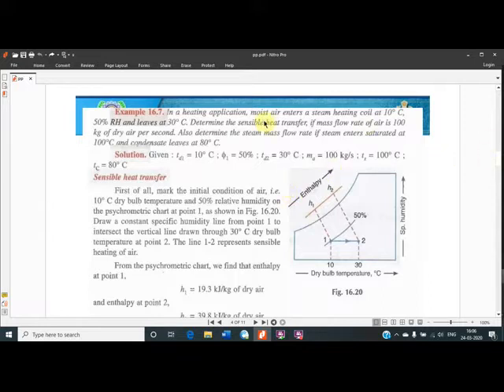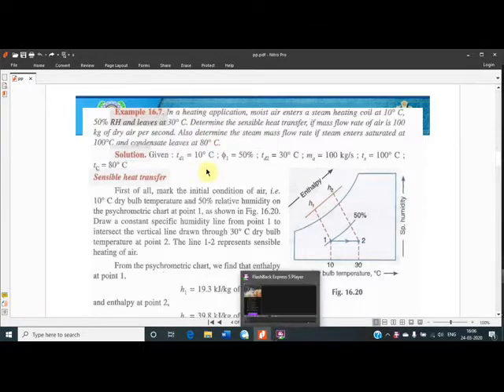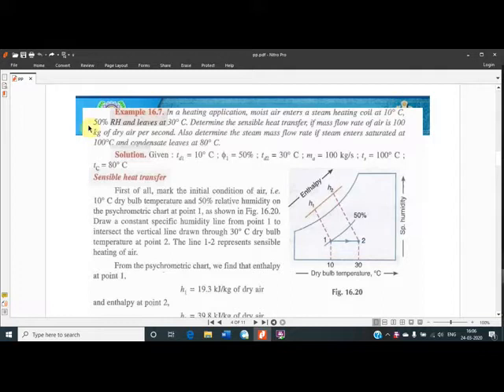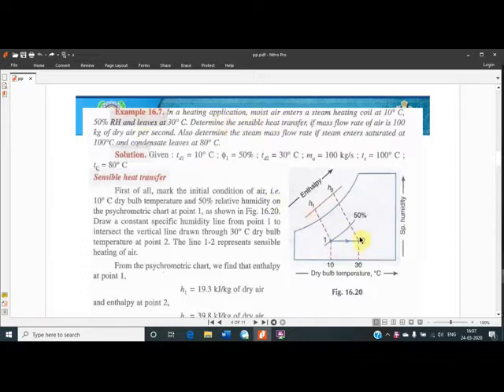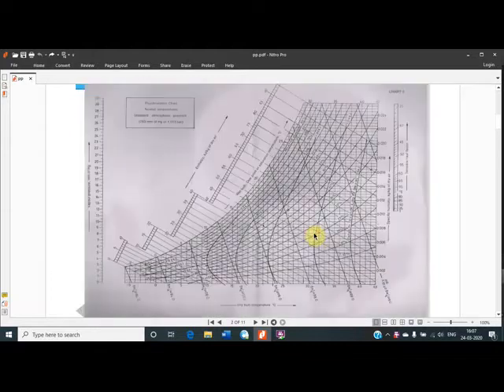I have taken a numerical example. In this heating application, moist air enters the coils at 10 degrees centigrade and 50% relative humidity, and leaves at 30 degrees centigrade. We need two data points to get a point on the chart. The air is entering at 10 degrees centigrade and 50% RH — you locate the 10 degree centigrade temperature and where it touches the 50% relative humidity curve, you get the first point. Then for sensible heat transfer, you move horizontally to the right.